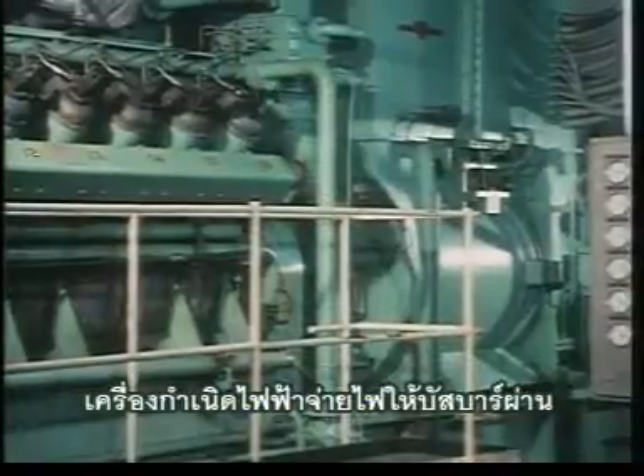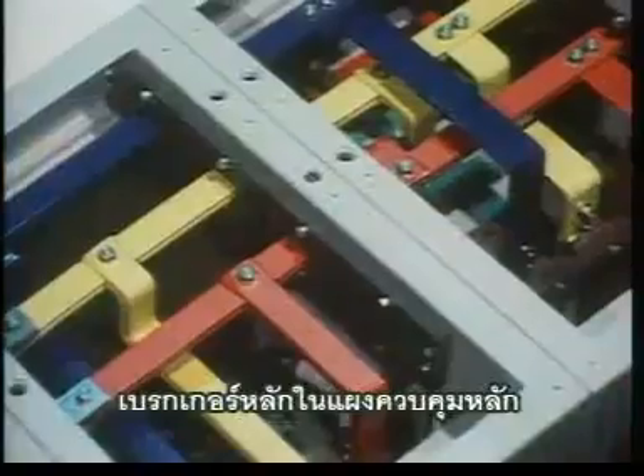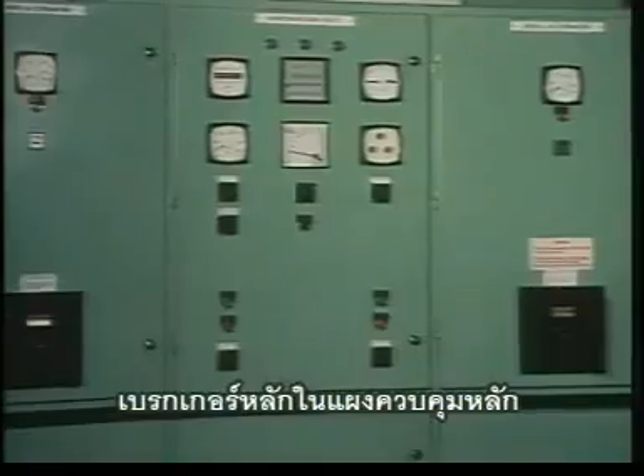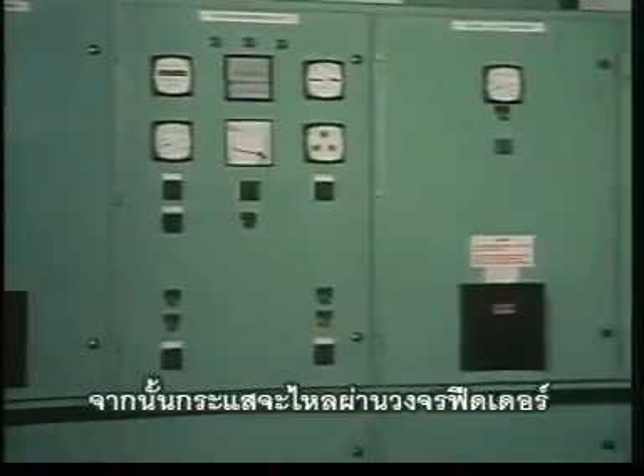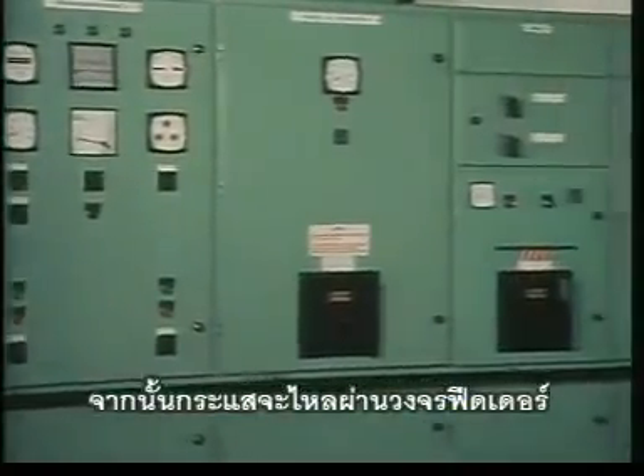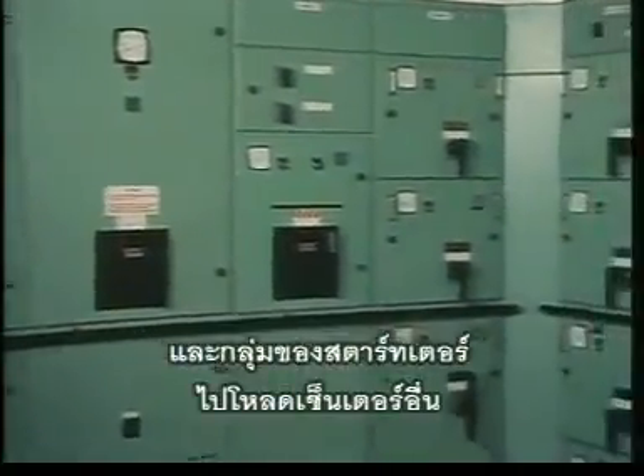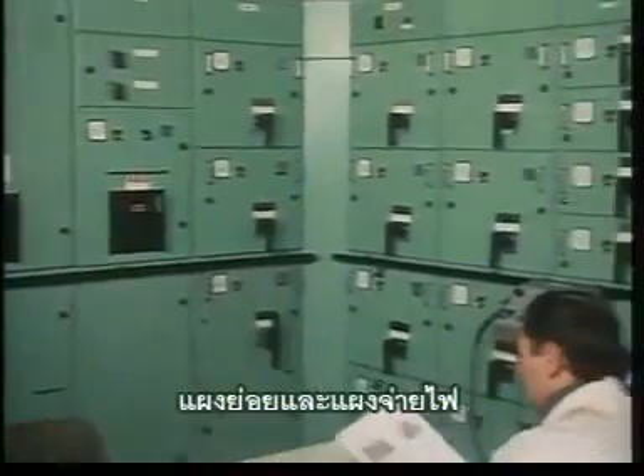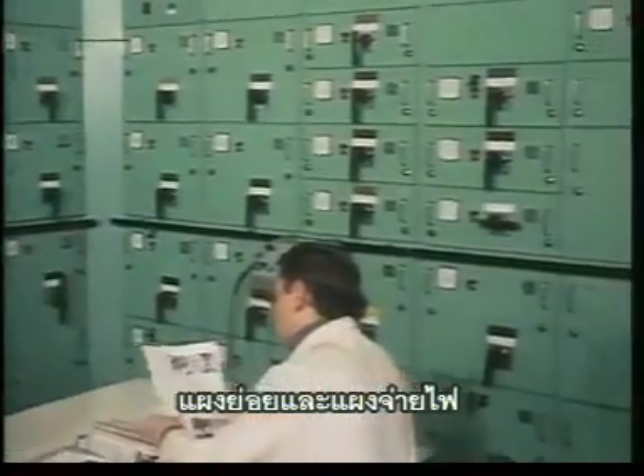The ship's alternators supply power to the bus bars via main circuit breakers in the main switchboard. And from there, bulk power is distributed through feeder circuits and group starters to other load centers, section boards and distribution boards.